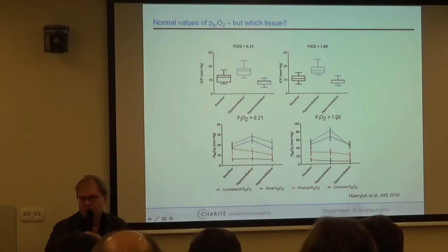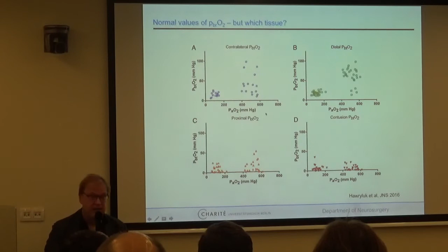The same at an FiO2 of 0.21, room air, or 100% oxygen. If you look at the probe position farthest away and do an oxygen challenge, oxygen on the probe stays low with room air and goes up with a very wide spread with 100% oxygen. This difference shrinks as you move closer to the contusion, at the rim of the contusion, where there's a little more scatter on these values. And if you're inside the contusion, there's no big change in brain tissue oxygenation, only in the arterial oxygenation. This is the way the probe behaves in the animal experiment.